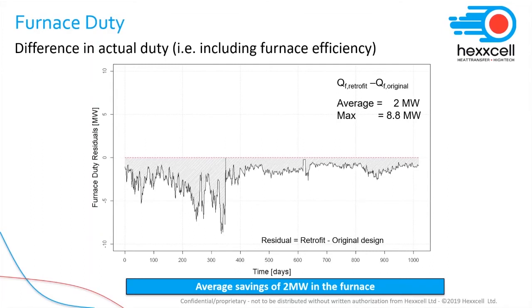So what is the overall impact of the new design on the furnace when we consider the entire network? The redesign is estimated to save 2 megawatts at the furnace, which is ultimately what you're interested in, as opposed to the 3 megawatts estimated when we consider the heat exchanger in isolation. This reiterates the importance of considering all the dynamic interactions in the network when performing this type of assessment.